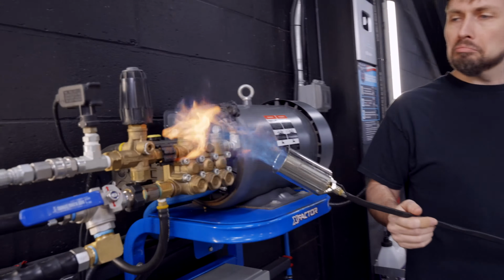But we're gonna leave the power on for me here right now just so I can show you what voltages are supposed to go to what things. You get your fused incoming power off your transformer, then it goes to the switch, from the switch to the input of your timer relay, and then your input goes to your timer, your digital timer, and your coil. And then these are your pressure switches, wired in series. You have your two common wires, one from each pressure switch, and then the one after the pump has the red and the blue.